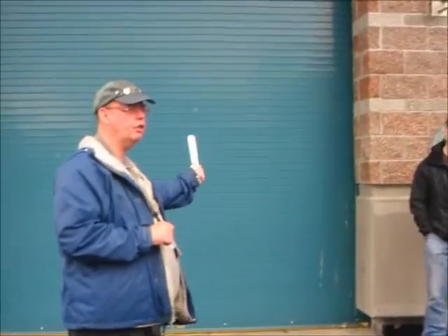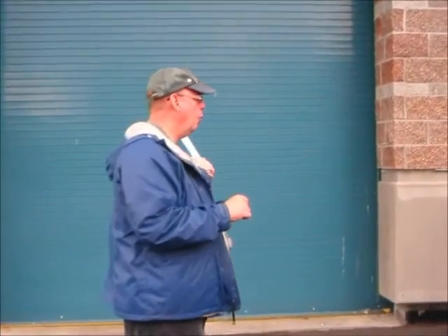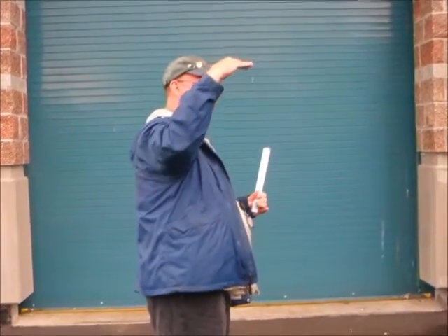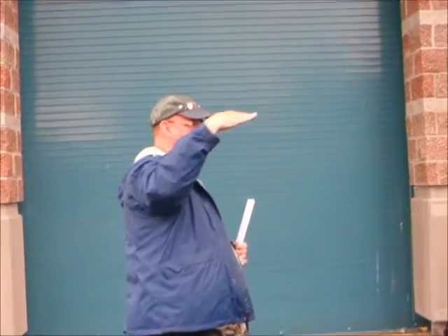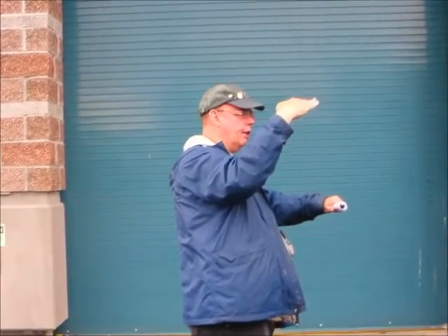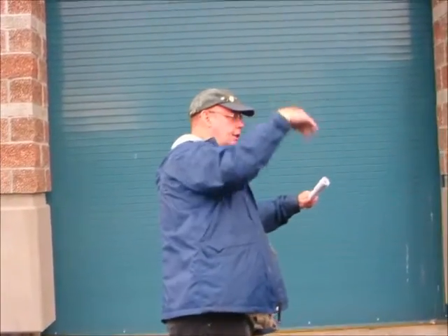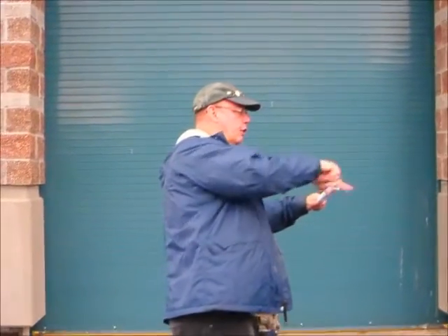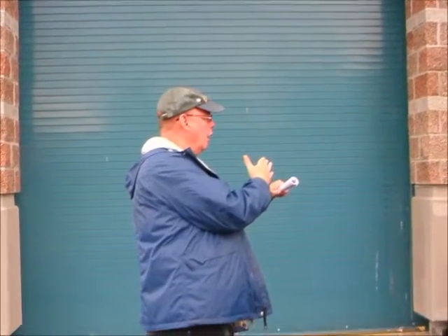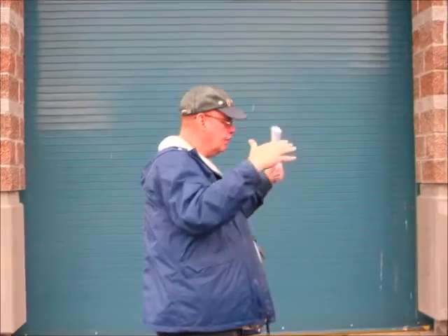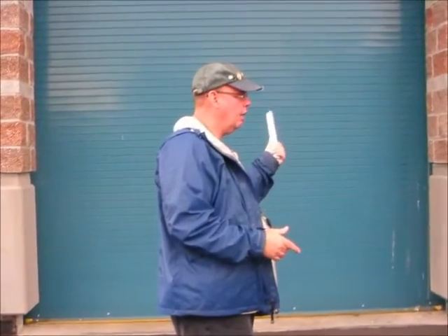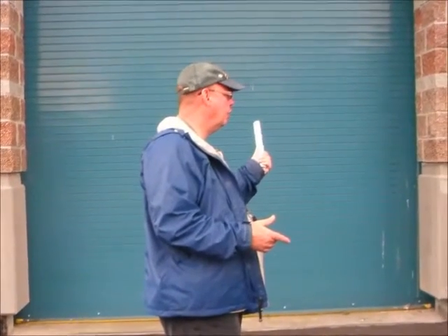So you're not really going to see the actual water coming through here, but I just wanted to let you know that this also incorporates a self-cleaning feature, as the wet wells are very narrow trench-style wet wells. As the water comes in, the water level stays even with the flow coming in, and then every so often we actually lower the wet well levels. When that happens, it exposes the slope, and the water will take a downward bend and increase in velocity and actually scour all the debris in the wet wells to the back end, where we have a large cleaning pump. So basically it sucks all that stuff up and sends it up to the headworks, and it's taken out up there. So instead of having to take our pump station offline for 2 weeks every 2 years or so, we actually just clean it on a regular basis, and it's no muss, no fuss.